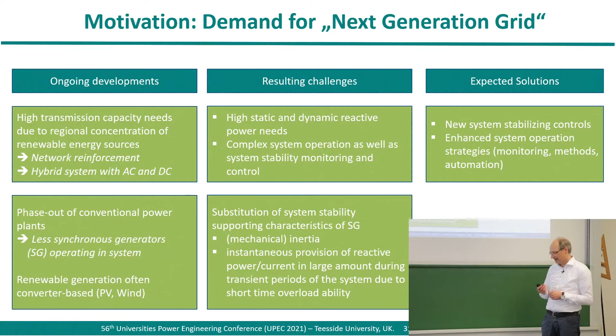In contrast, renewable generation is usually converter-based, so there's a different technical interface to the network. However, the actual network is mainly designed based on the existence of synchronous generators with some of their special characteristics — based on their power synchronization behavior, but also on the mechanical inertia they provide and on the instantaneous provision of reactive power and current if anything in the network changes, according to their stabilizing effect on the network.